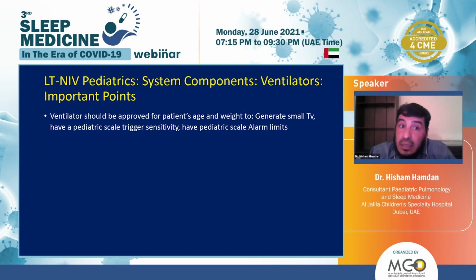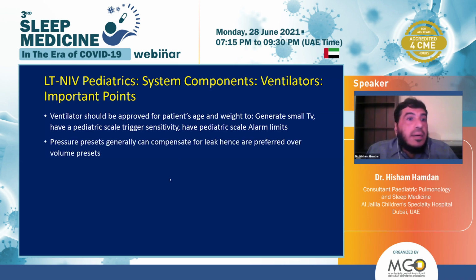Also, is the trigger sensitive enough for a pediatric kid or even a neonate? And is there an alarm limit that is low enough to be useful in pediatric patients? And then pressure presets generally can compensate for leak. One issue with non-invasive ventilation is leak. And pressure presets, namely BiPAP, can, to a good degree, compensate for the presence of mask leaks. So they are much more preferred over volume presets.